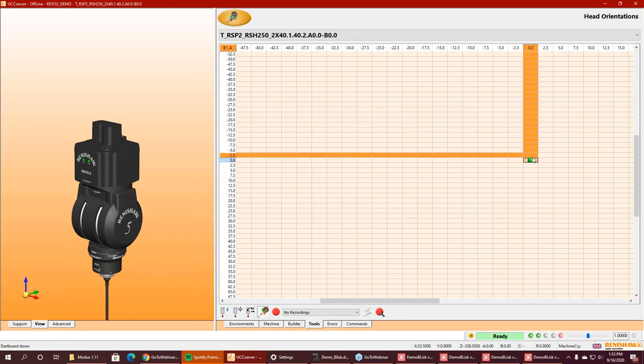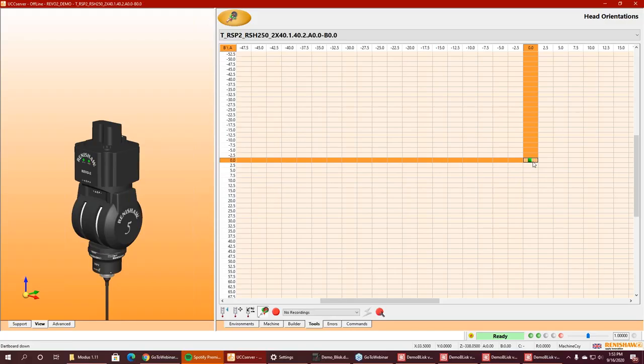And how often do you recommend that people requalify the tool? Because, obviously if I'm just using an A90, B90 kind of probe or something for my traditional 3-axis inspection, that may only take 10 or 15 seconds or so maybe to inspect. So if I have to requalify this whole head, is that something I have to do every hour, or is it less significant than that? Oh, it's definitely less significant. It really depends on your environment. I've seen places do it every 8 hours. I've seen people do it every 24 hours. It's definitely not something that has to be done every hour, though. Good. Well, that definitely cuts down on some time there if it's only 20 minutes for the whole head and it's only every day or so. Right.